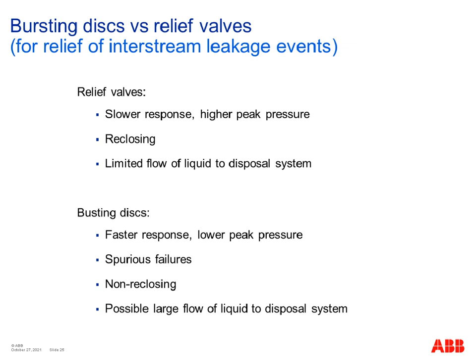So then you're in a situation where you're losing possibly large amounts of liquid in your system to a disposal system, and that may cause you problems in and of itself. That can be an issue for the plant to deal with. And obviously, the bursting disc would have to be replaced before the plant could be returned to what it was before that spurious failure occurred. Whereas with a relief valve, it will reclose, and you're back to where you were before.